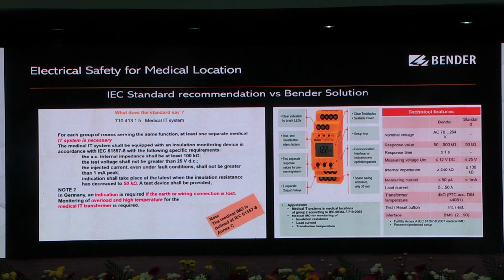Because during operation time you cannot switch off the devices, you have to identify the fault online. That is the reason the IEC says you have to inject less than 1 milliampere in the system to identify the fault. So according to the standard, we are following the same.